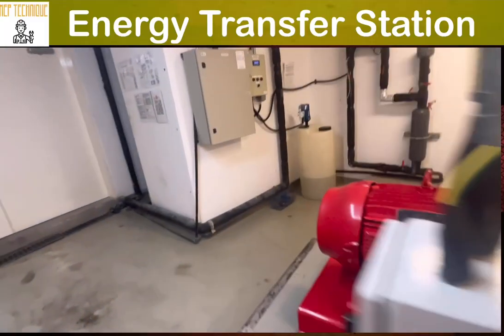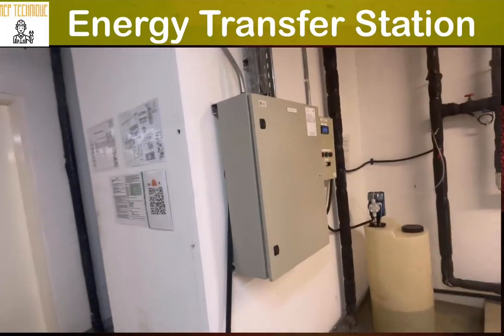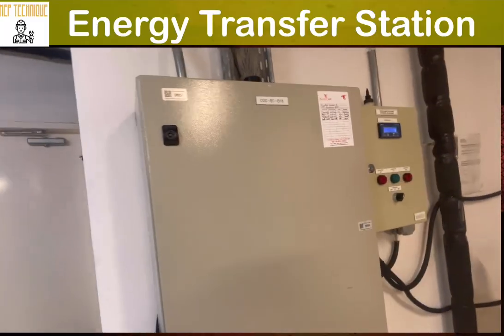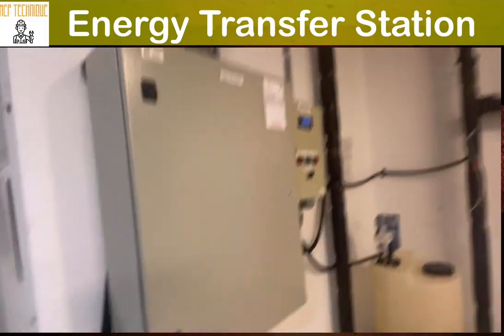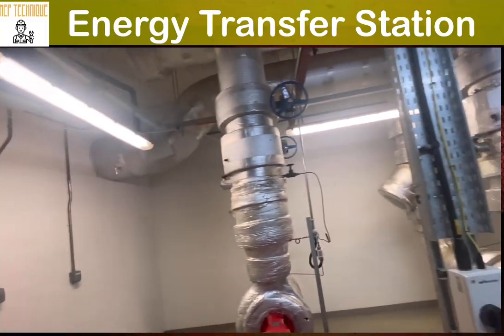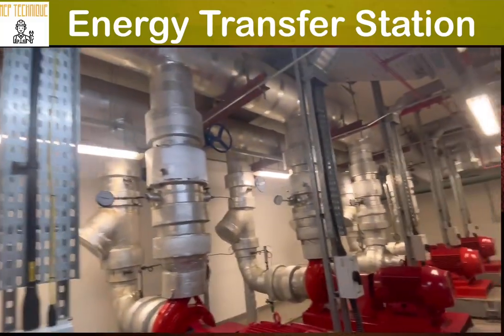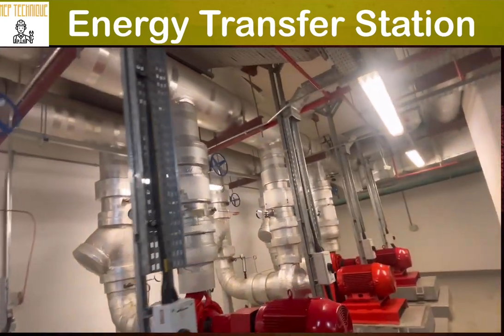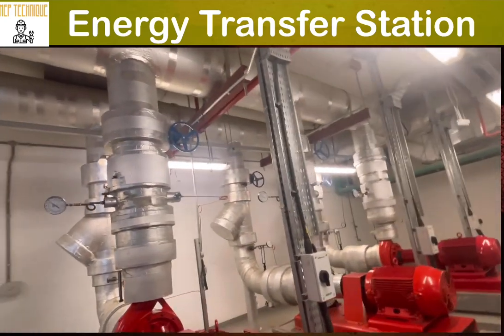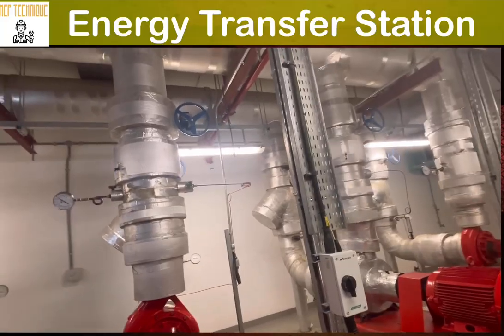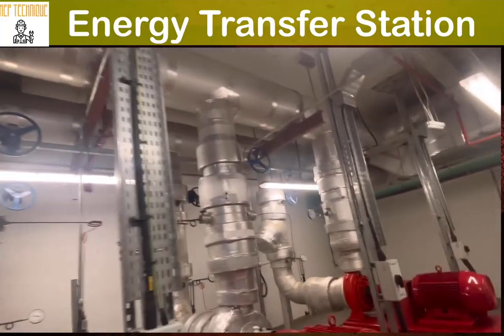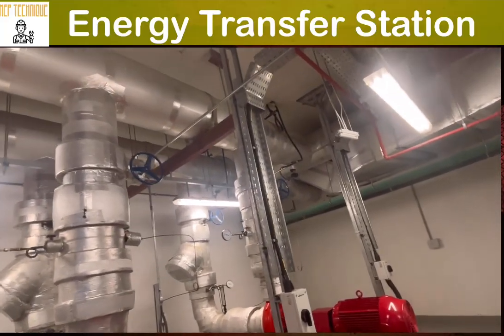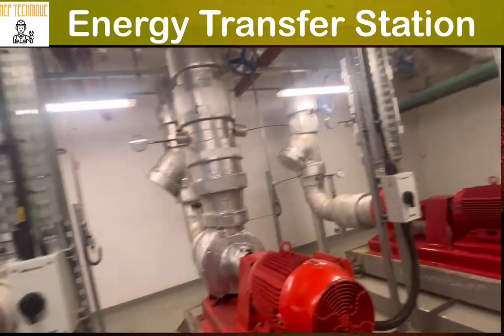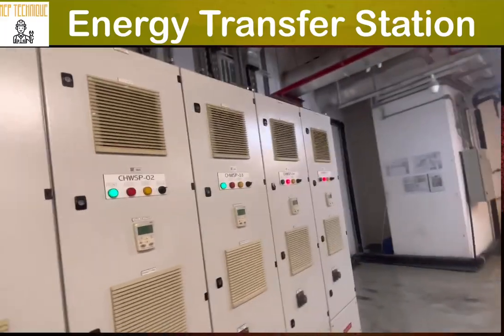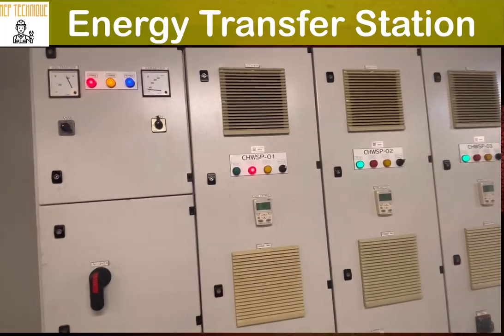DDC means direct digital control. You can see there is a DDC panel, where all the pumps are integrated with the differential pressure transmitter connected across the chilled water, and it is continuously monitoring the differential pressure across the chilled water. When the differential pressure decreases, then our VFD, this is the VFD panel, will be ramped up.